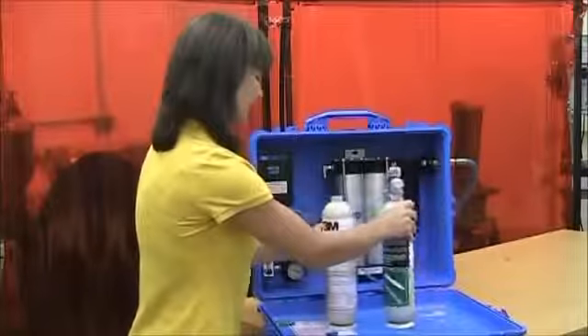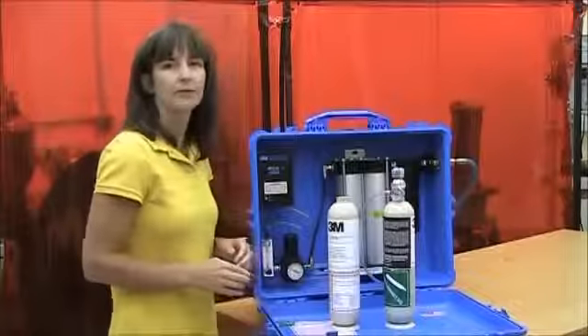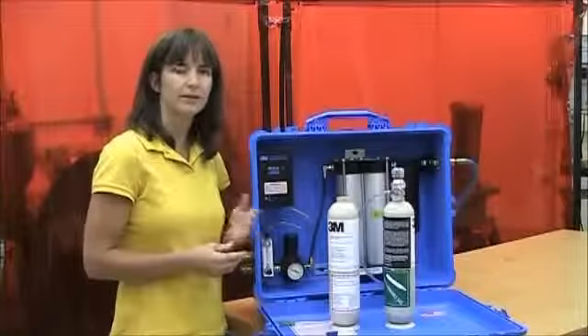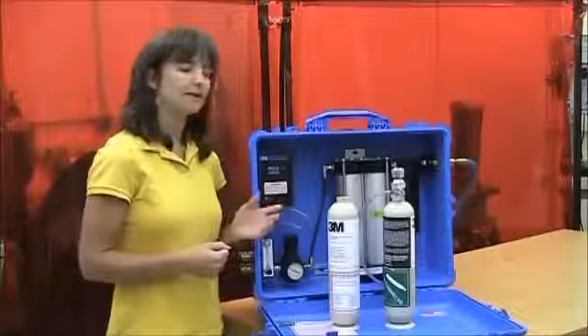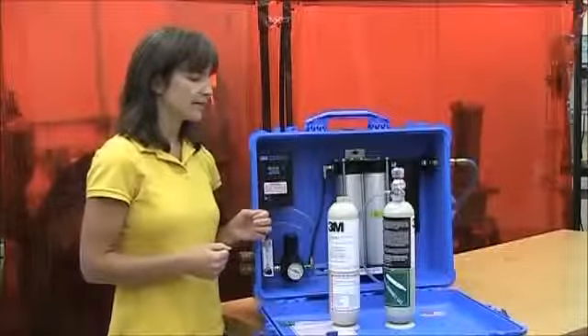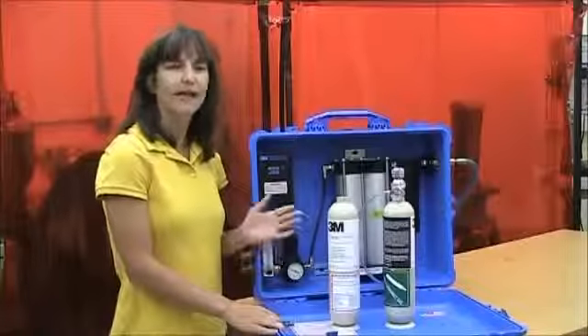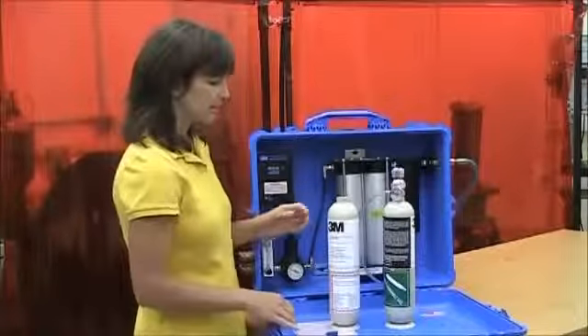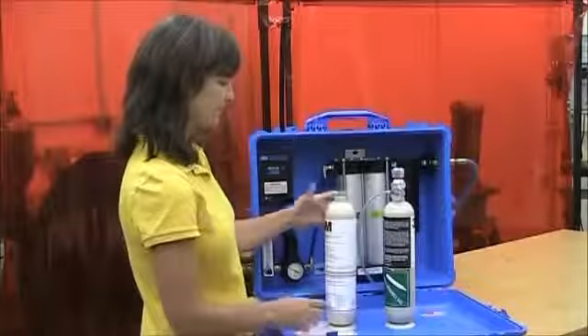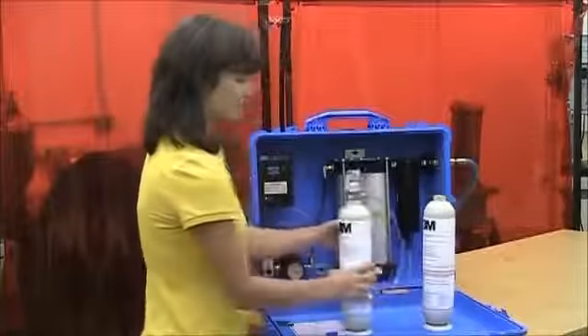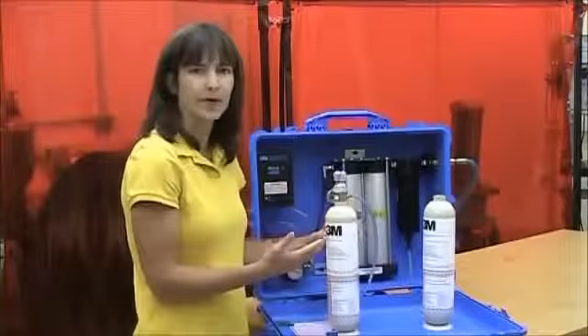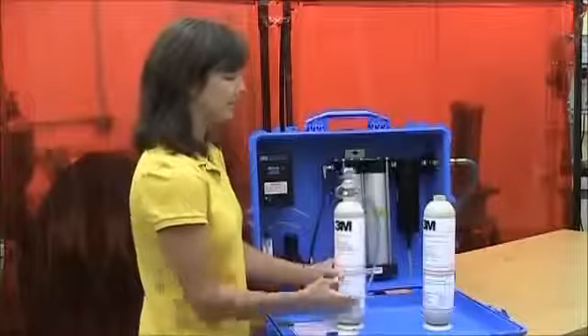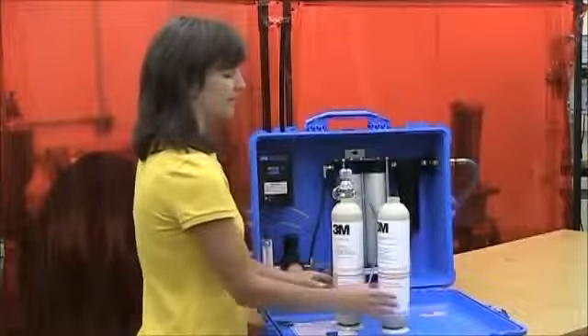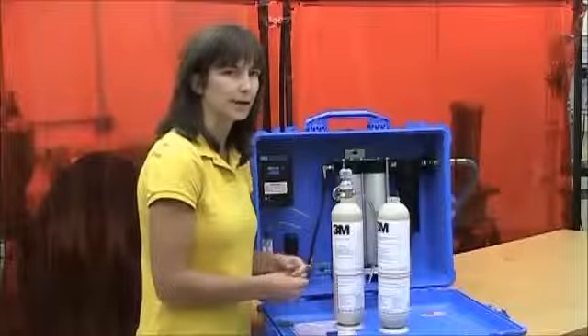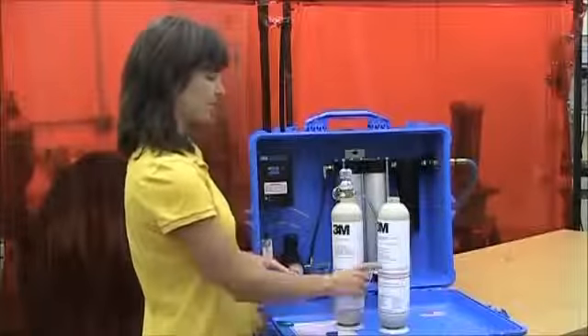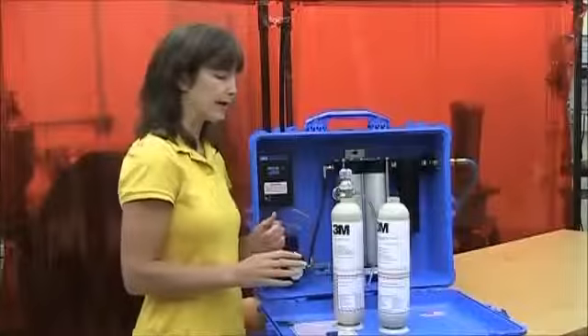Okay, so for calibration frequency, you're going to want to calibrate every 2 weeks when the monitor is new for the first month. After that, you'll calibrate monthly. Unless you don't use the panel very often, then you're just going to calibrate the monitor prior to each use. So the calibration itself consists of two parts. You've got a zero gas, so zero air, it's carbon monoxide free. It's actually a nitrogen gas. And then a carbon monoxide, in the 3M kit, it's a 95 part per million carbon monoxide gas.